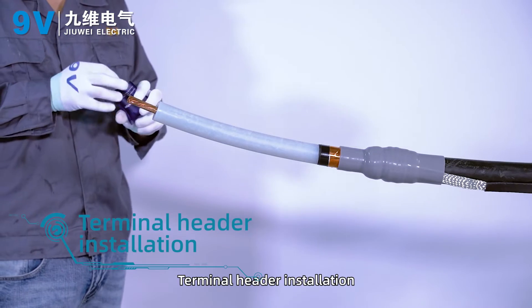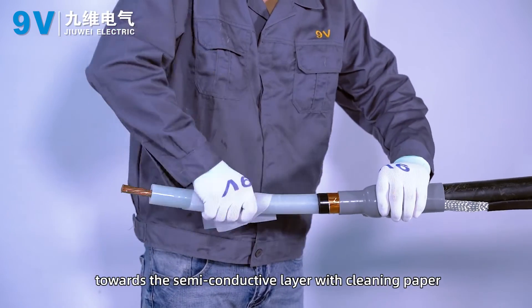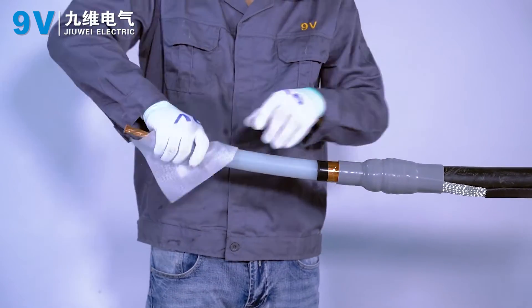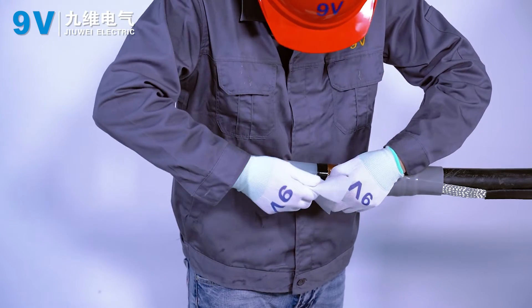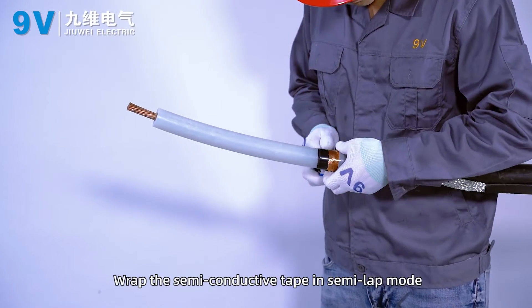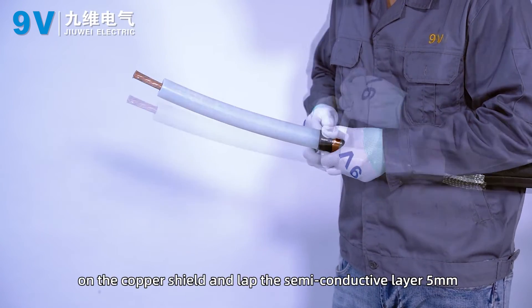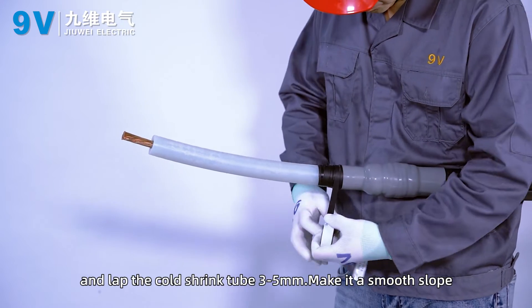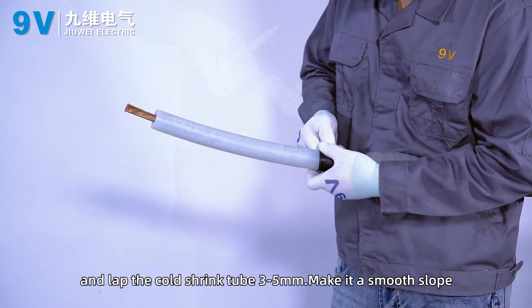Terminal header installation. Clean the surface of the insulation layer towards the semi-conductive layer with cleaning paper. Wrap the semi-conductive tape in half-lap mode on the copper shield, lapping the semi-conductive layer 5 mm and lapping the cold shrink tube 3 to 5 mm. Make it a smooth slope.